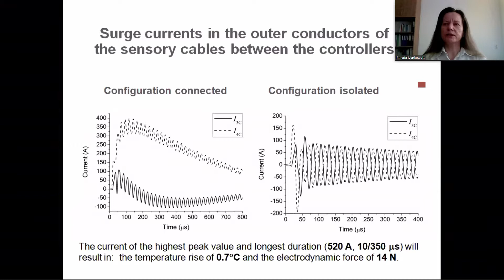To assess the threats of thermal or electromechanical effects of the surge currents on the cables, the current of the highest peak value and the longest duration was taken into account, which is in the case of the connected configuration. But even in this case, the estimated values of the temperature rise and the electrodynamic force are low enough that they will not cause damage to the cables.